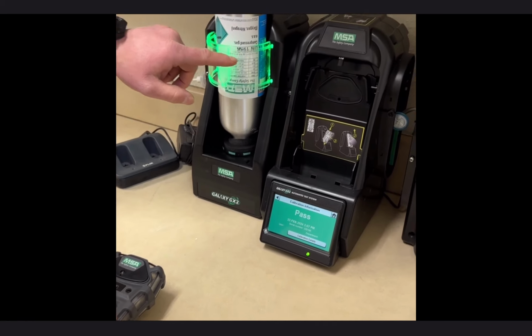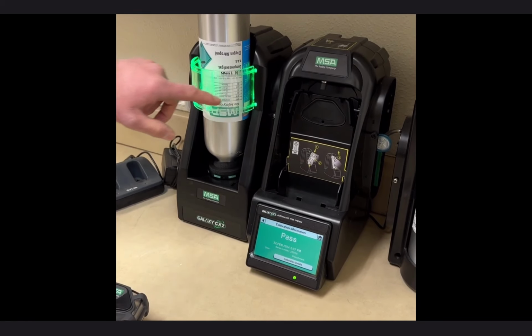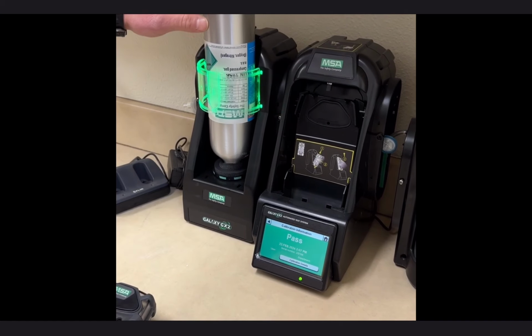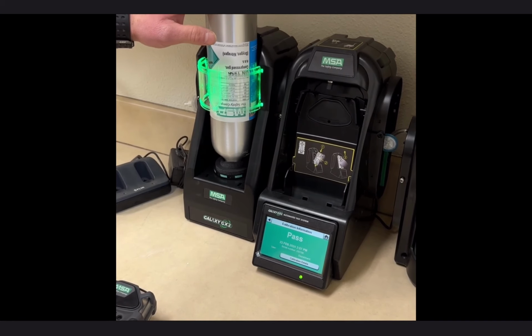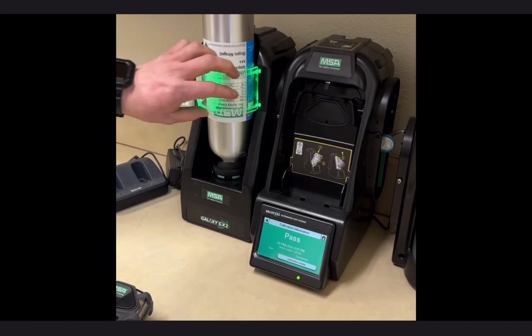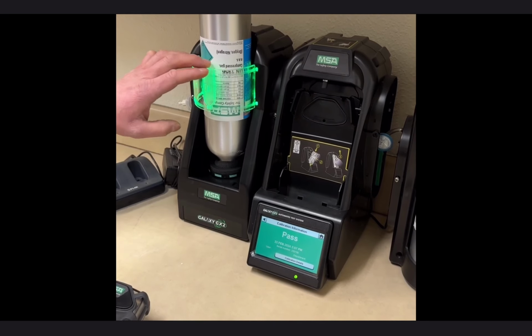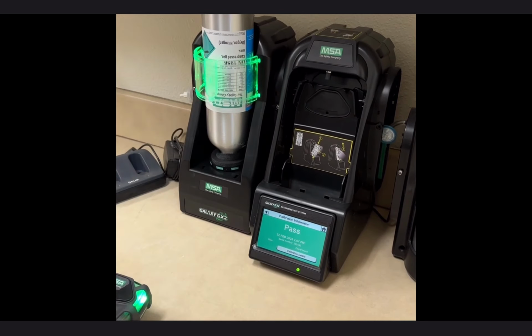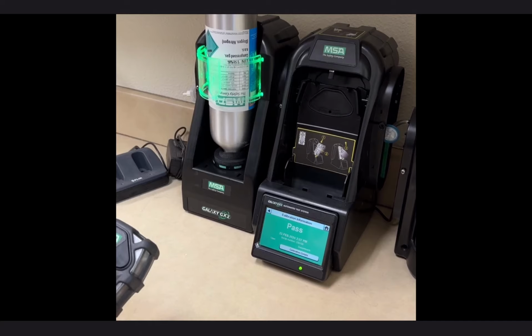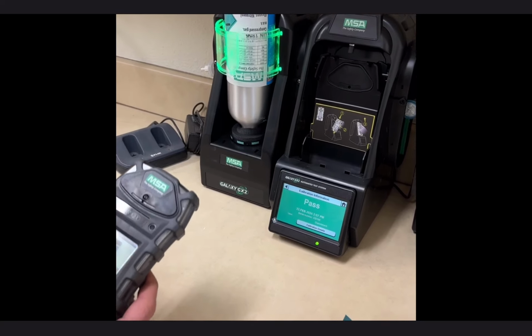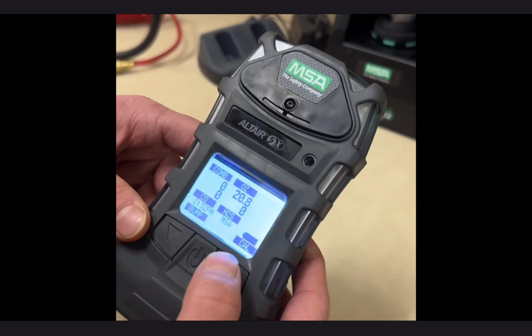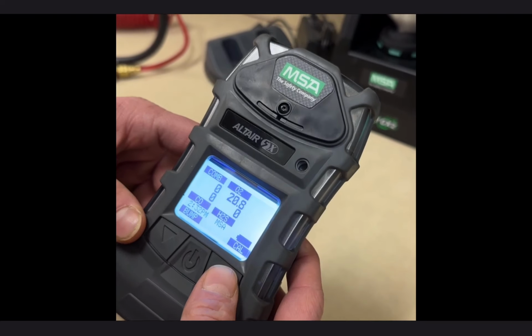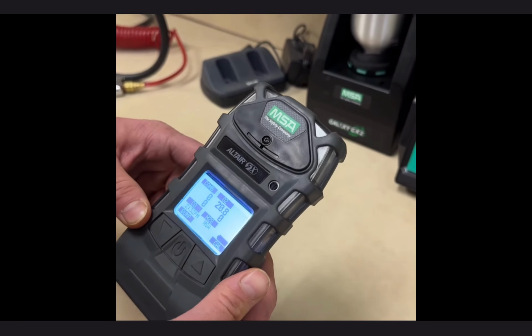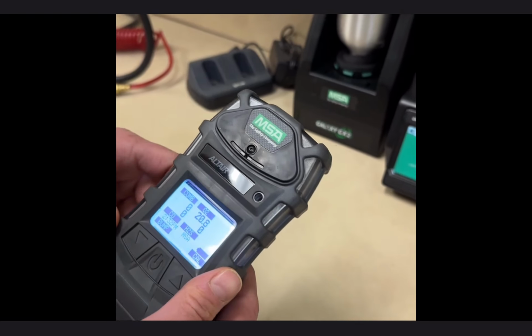This green ring just tells you that the calibration bottle is good. It's basically measuring the expiration date. So if this is red, you don't have a calibration system that's ready to be calibrated, but if it's green, it's good to go. You need to turn it on, and you don't really need to do anything else. If you wanted to force calibration, there is a button right there for calibrate that you hold down and you can force it to calibrate. But by putting it in the machine, it'll calibrate automatically.